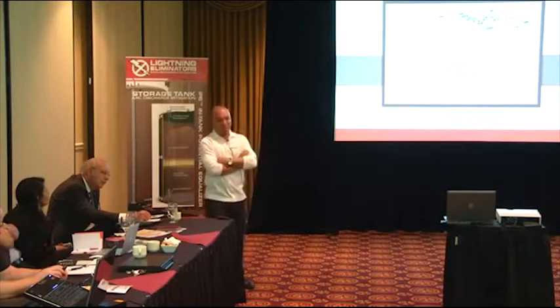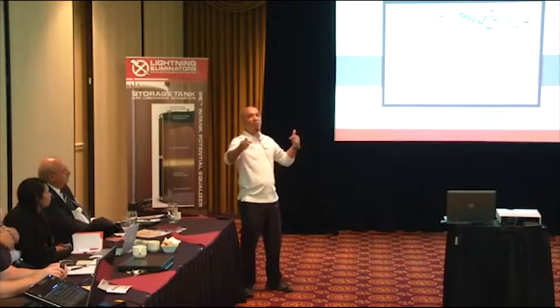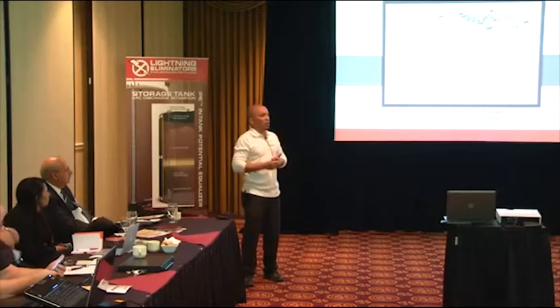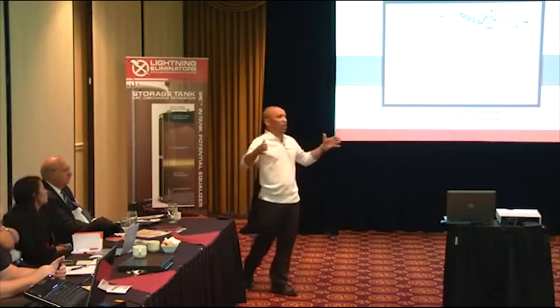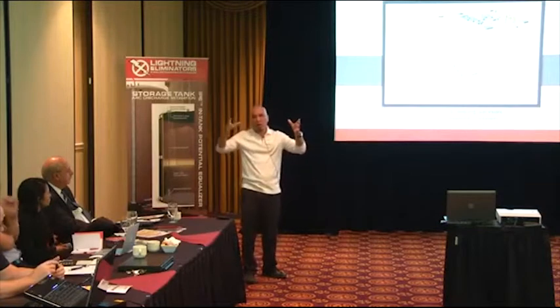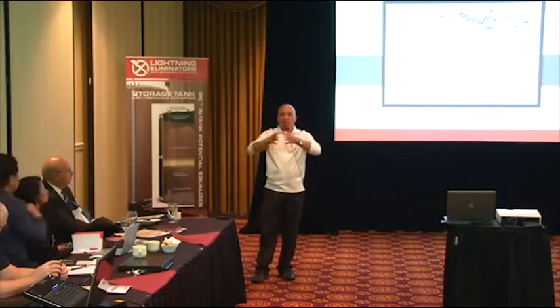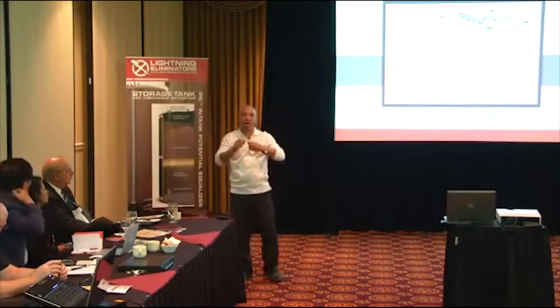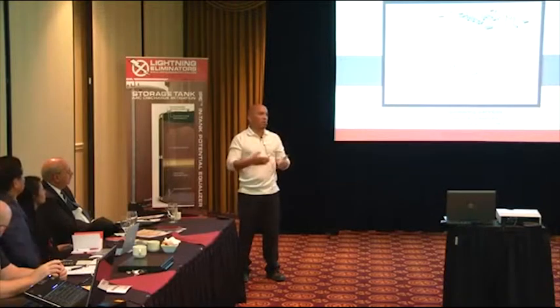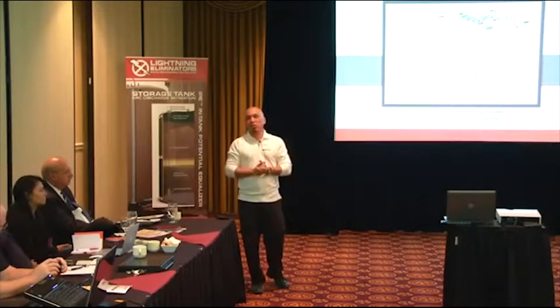I have seen, and I just came back from one, I was out of the country, where they went to test the grounding system and they had 80 feet of wire to do the ground impedance test. 80 feet. That was it. They were measuring tanks, each tank over 350 feet in diameter. You remember when Nate was talking about the volume of influence: the tank is essentially a 350-foot ground rod, and they're not even getting out of the influence of that grounding system, so what they're reading is completely false. But they're not telling the customer that. The customer doesn't know. So for $7,000 a day, the customer just paid for absolute garbage.